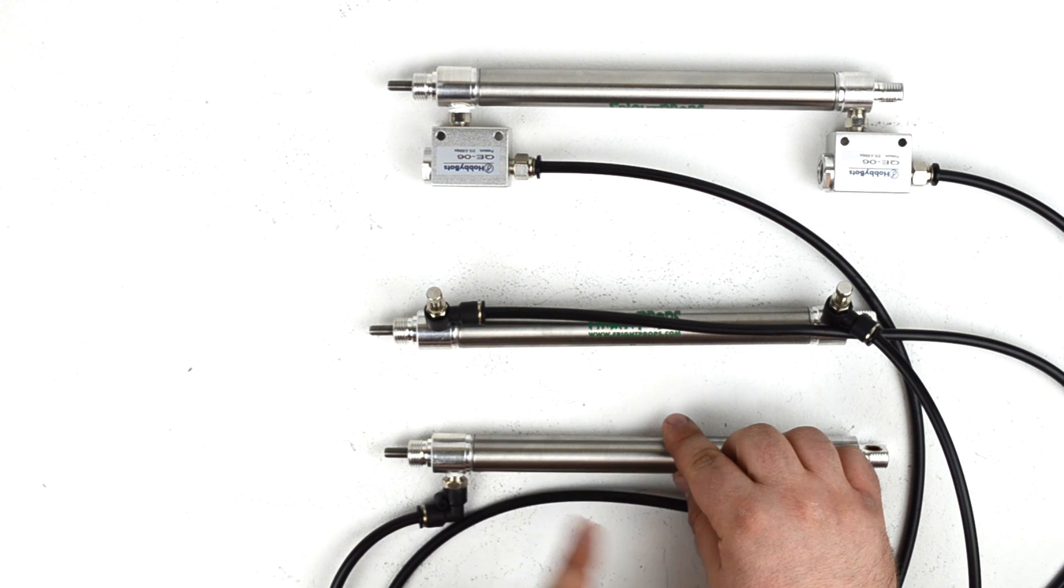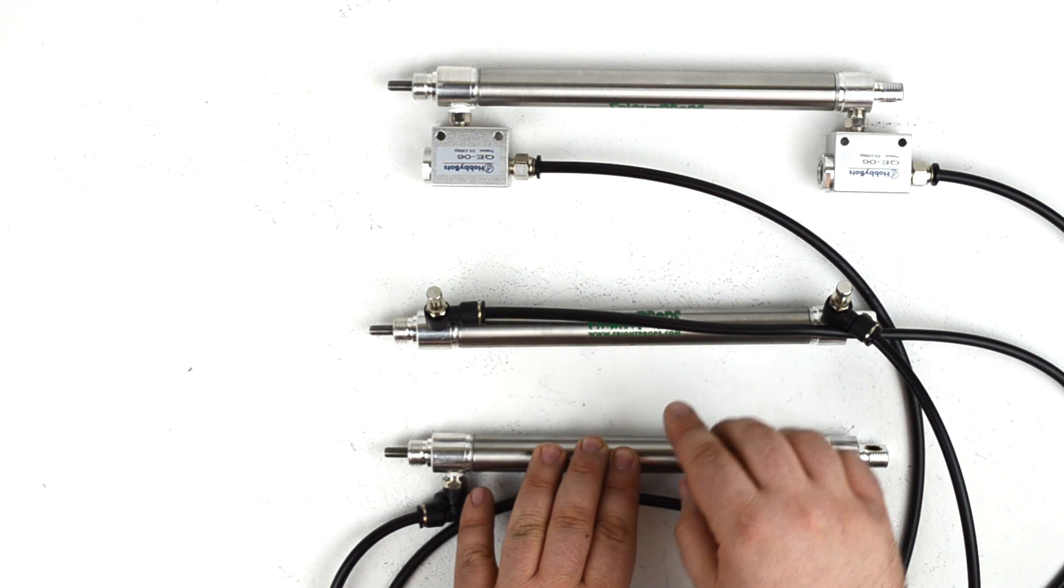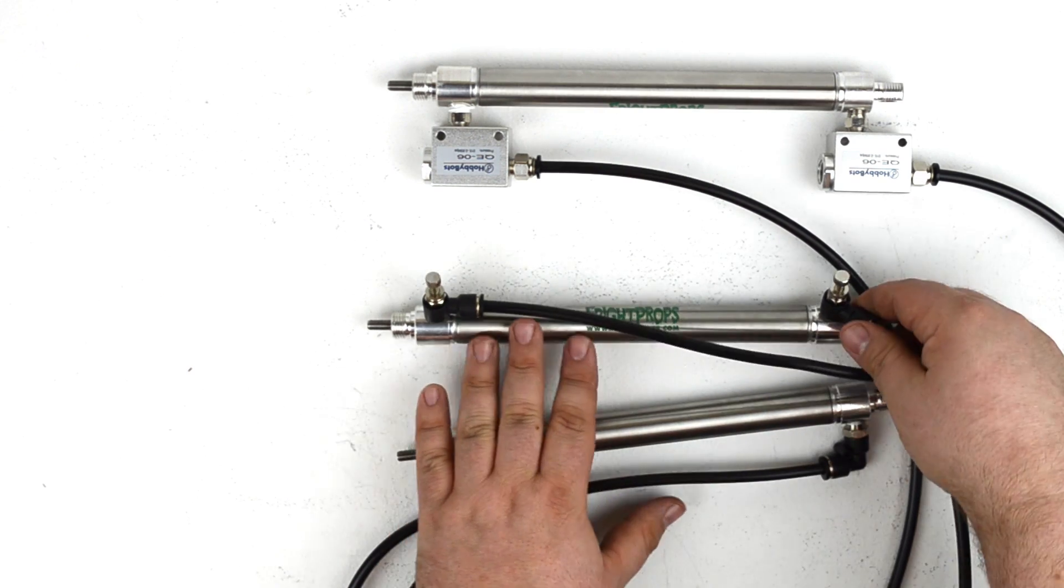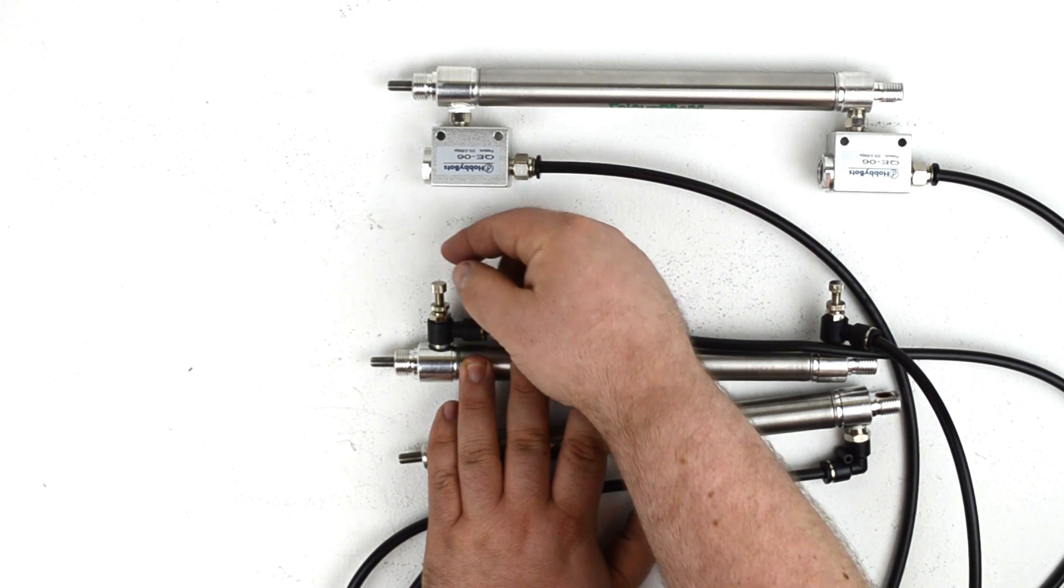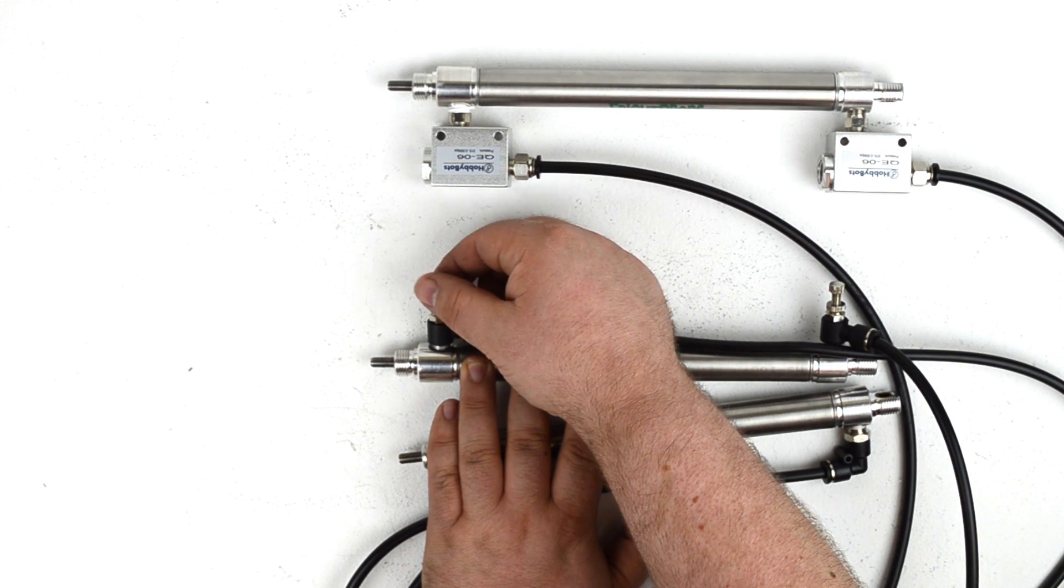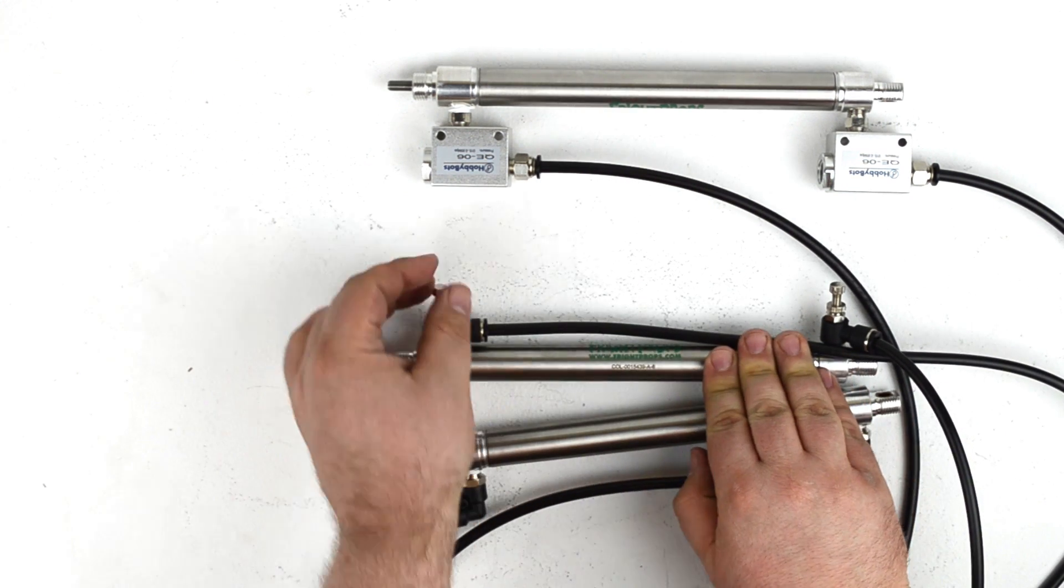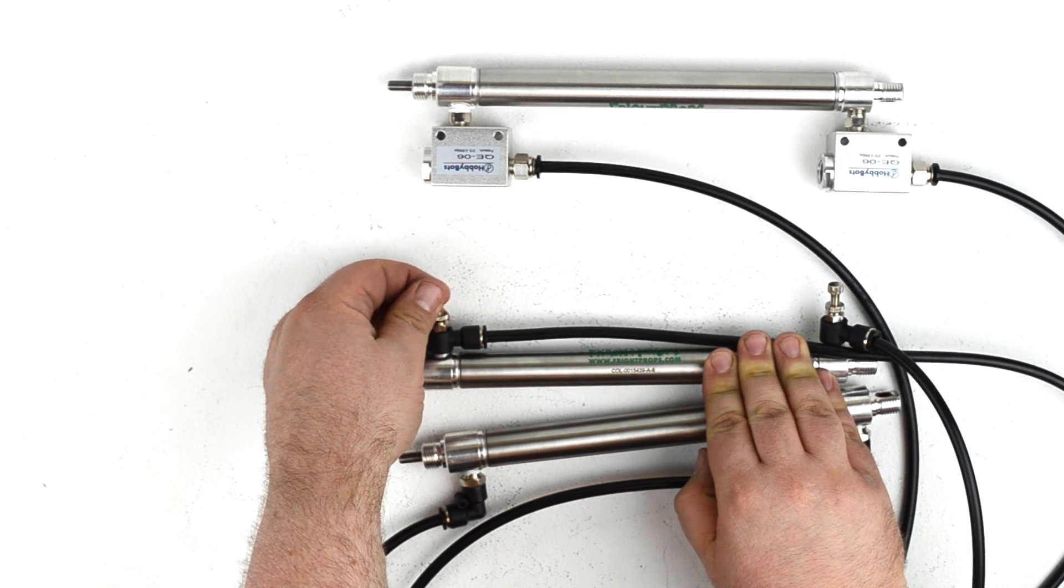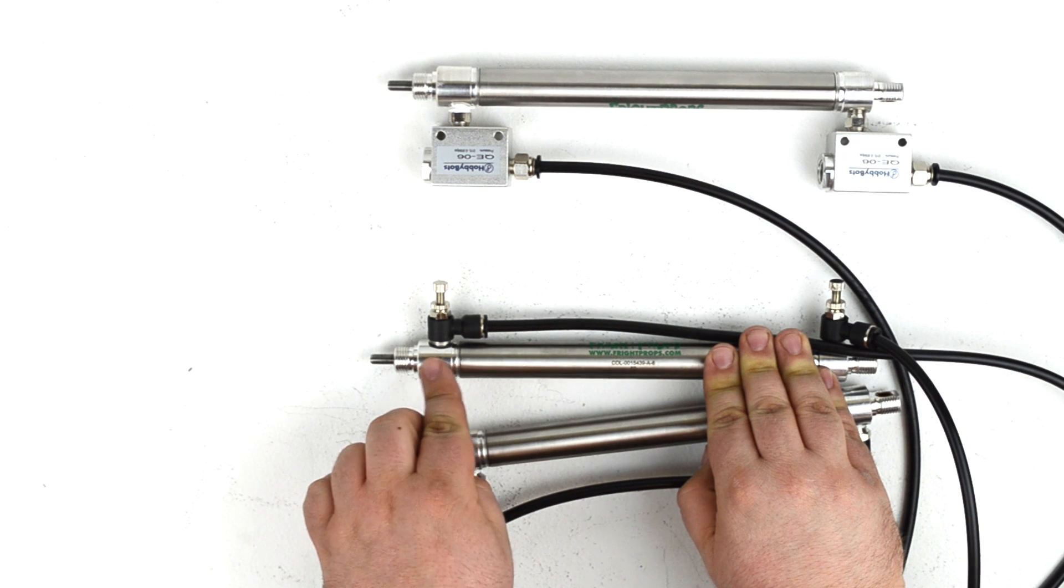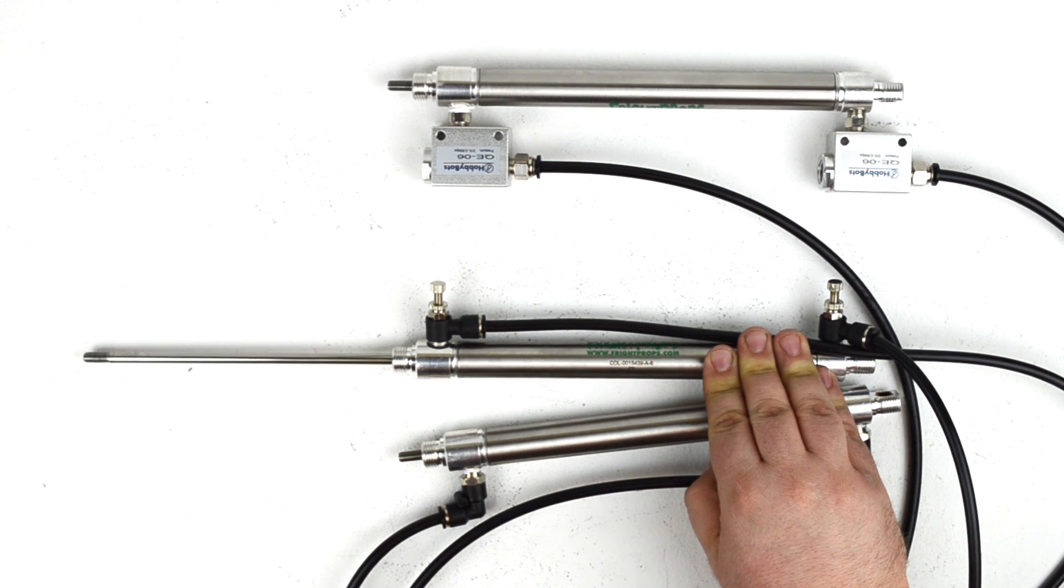Now let's say you wanted to slow that down, you wanted the cylinder to extend more slowly or retract more slowly. To do that you would use flow control fittings, which we have installed on the second cylinder here. As you can see, these fittings have a needle valve, a dial that you can turn in order to meter the flow of air going into the cylinder. So as you turn the needle valve and tighten up the passage of air through the fitting, the cylinder will extend and retract more slowly.